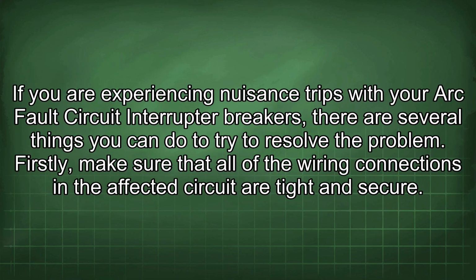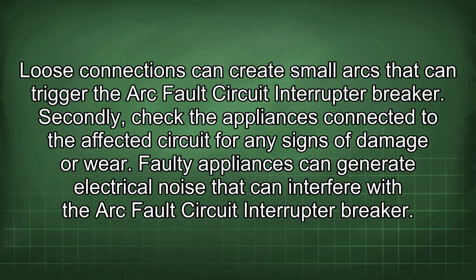If you are experiencing nuisance trips with your arc fault circuit interrupter breakers, there are several things you can do to try to resolve the problem. Firstly, make sure that all of the wiring connections in the affected circuit are tight and secure. Loose connections can create small arcs that can trigger the arc fault circuit interrupter breaker. Secondly, check the appliances connected to the affected circuit for any signs of damage or wear. Faulty appliances can generate electrical noise that can interfere with the arc fault circuit interrupter breaker.